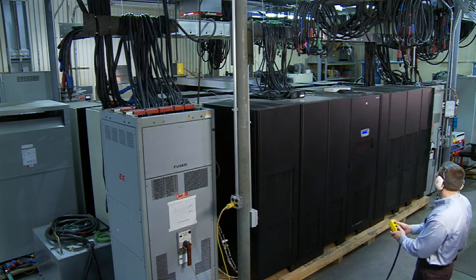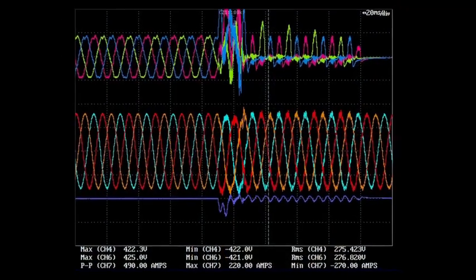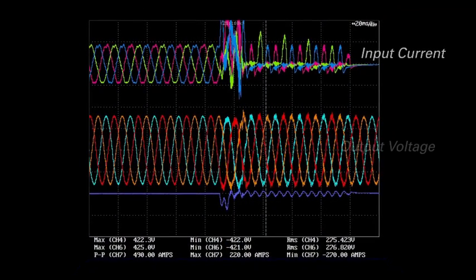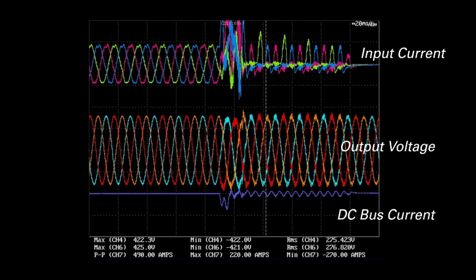Fault! The images displayed here show the fault that we just applied to the unit. They represent the battery plus to ground condition. They demonstrate the robustness of the 93-95 product. The unit emergency transferred to bypass and maintained the critical load.